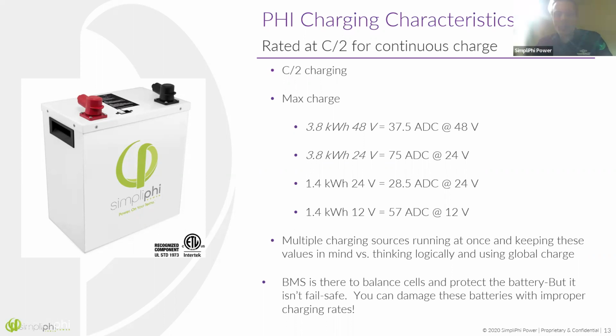We have to make sure that if there are multiple charging sources running at once, we keep these values in mind. So if you have a couple of SM80s, a single SM80 is capable of charging at 80 amps. We need to make sure that we're not overcharging these batteries. And if an individual battery can only handle 37.5 amps, then we have to make sure that we have enough batteries in the bank. So that's what we mean by keeping these values in mind as you're designing systems.